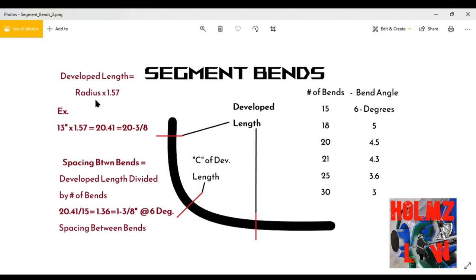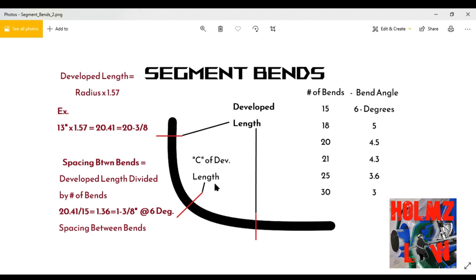Now here's an actual example. Developed length: 13-inch radius times 1.57 equals 20.41, which rounds off to 20 and 3/8 inches — that's our developed length. When we lay it out, we put two marks 20 and 3/8 apart, then find the center — which is 20 and 3/8 divided by 2. Mark that center on the conduit. Important: these two marks are temporary marks, not bend marks. They're just to help you lay out your conduit.